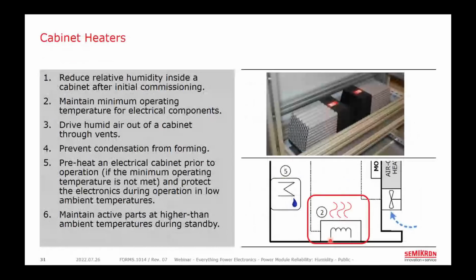Electric air heaters are used for heating the air inside an electrical cabinet. And these can help reduce the relative humidity after commissioning or long periods of downtime, as we just discussed. And if the water vapor has a pathway out of the cabinet, running these heaters for long enough can lower the absolute humidity and dry the internal air, just as you would in an oven in your kitchen.